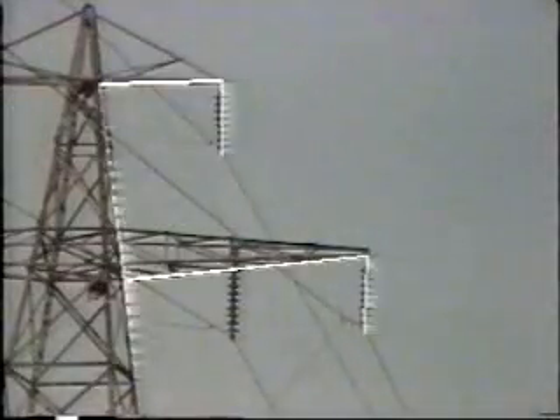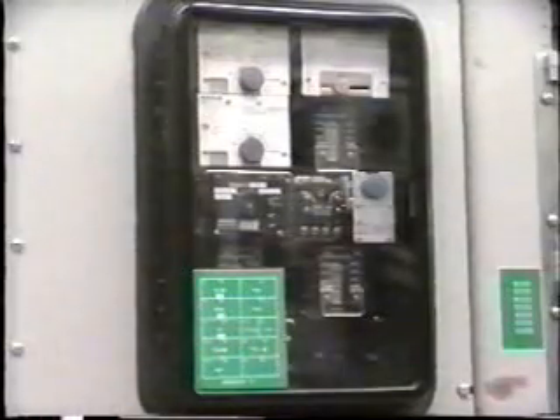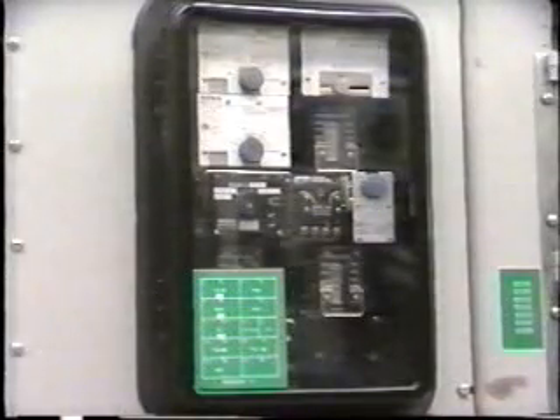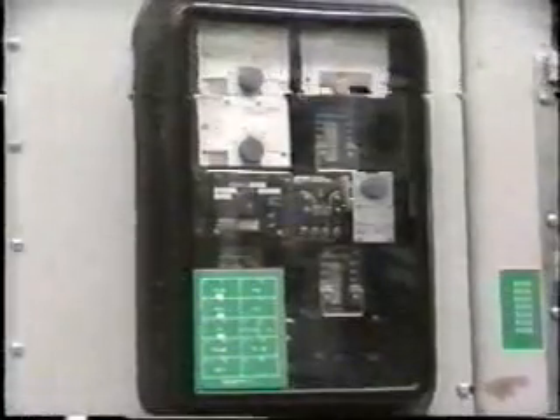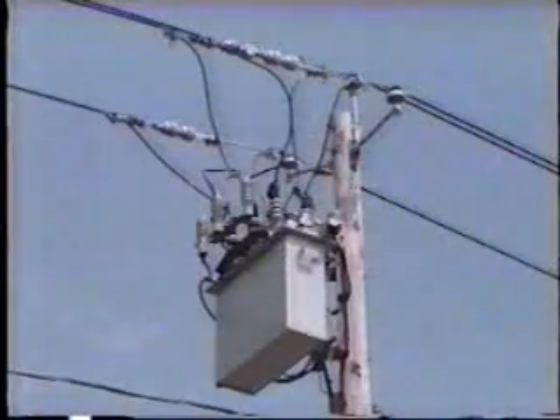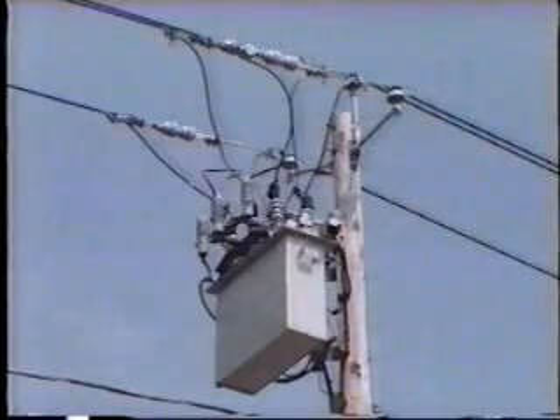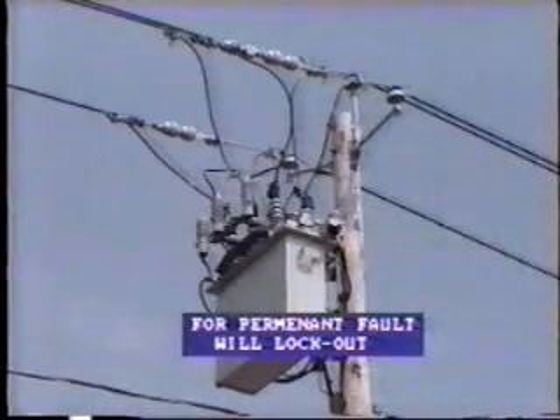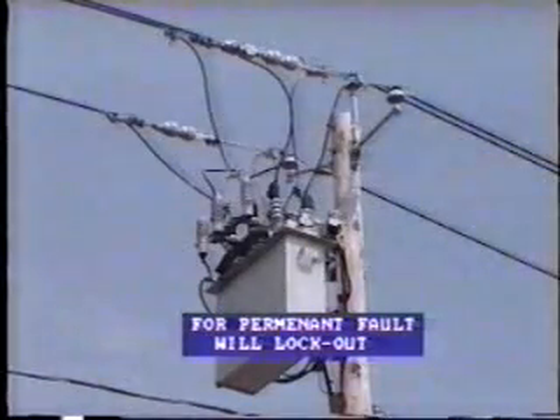A fault due to a lightning stroke is temporary in nature, because as soon as the circuit breakers are opened, the fault disappears. For this reason, reclosing arrangements are used on the vast majority of lines. This may take the form of a reclosing relay on the feeder breaker, or a recloser switch which is usually installed out along distribution lines. If the fault is a permanent fault, then the breaker will open again and the recloser or reclosing relay will lock out so as to leave the line isolated.